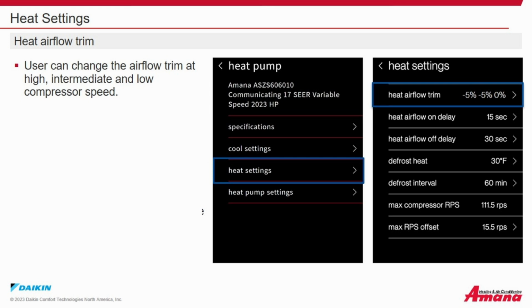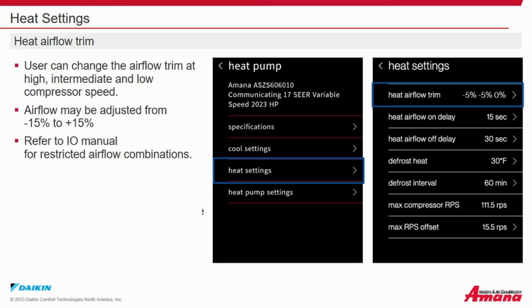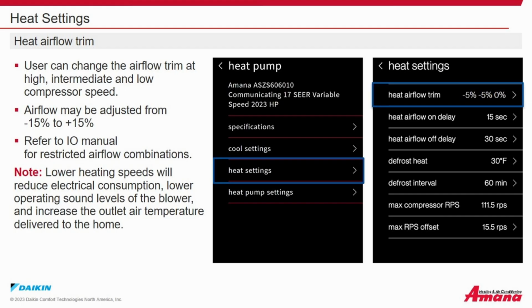Heat settings. Heat airflow trim. A user can change the airflow trim at high, intermediate, and low compressor speed. Airflow may be adjusted from -15% to +15%. Refer to the installation operation manual for restricted airflow combinations. Note, lower heating speeds will reduce electrical consumption, lower operating sound levels of the blower, and increase the outlet air temperature delivered to the home.